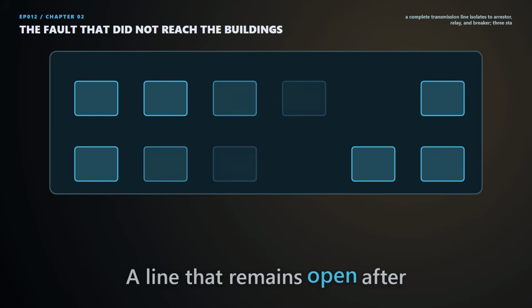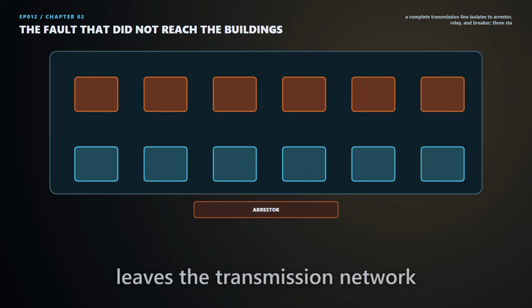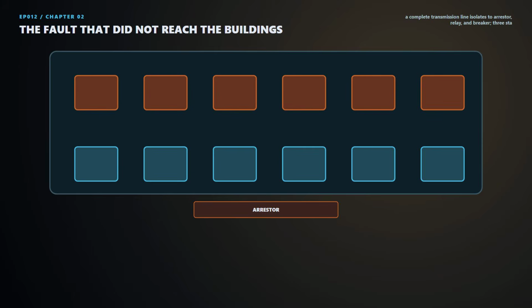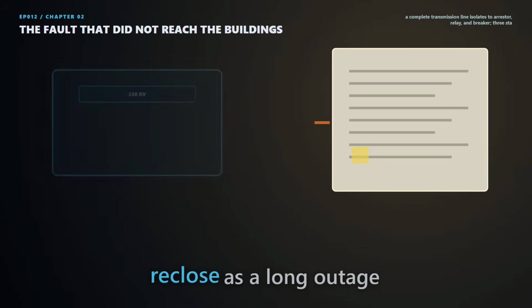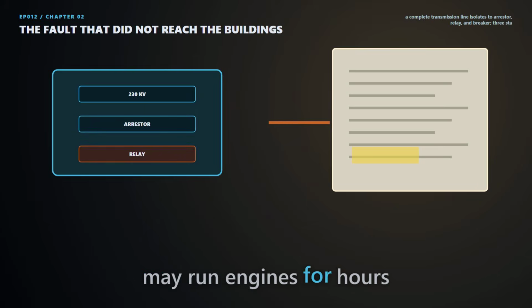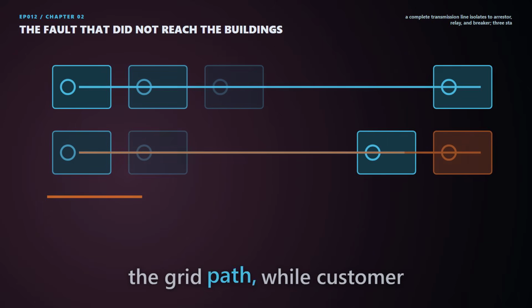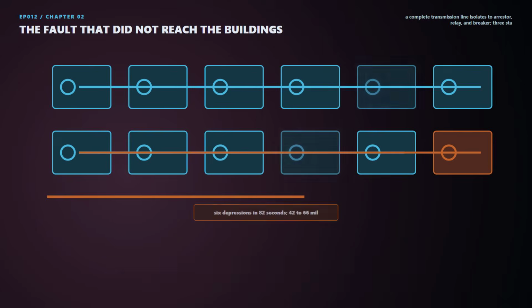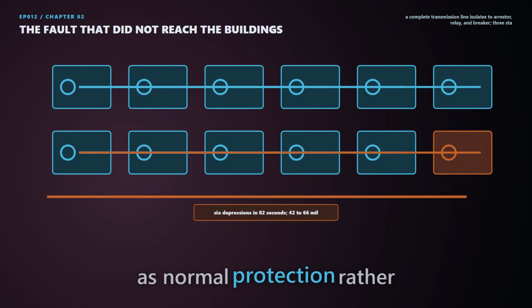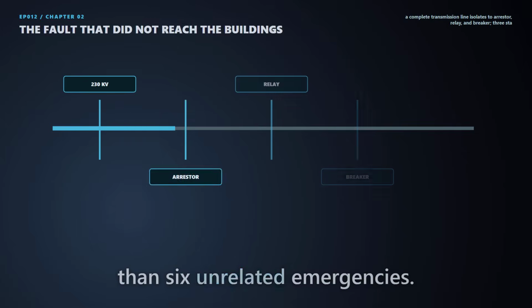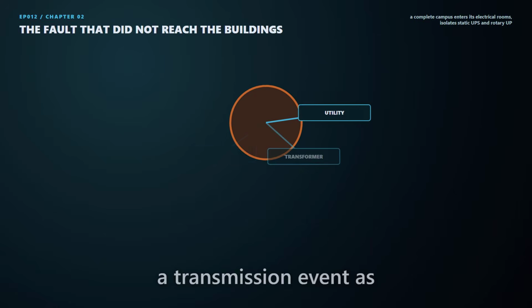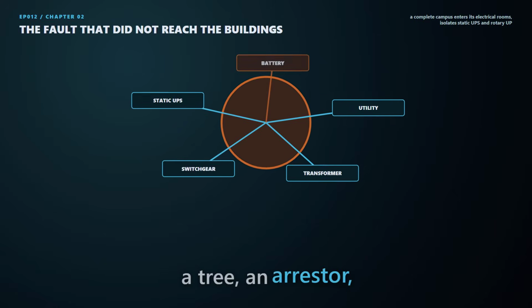A line that remains open after every temporary contact leaves the transmission network weaker until crews investigate. A campus that treats every reclose as a long outage may run engines for hours after the line is healthy. Operators need enough attempts to recover the grid path, while customer controllers need one published sequence they can recognize as normal protection rather than 6 unrelated emergencies. A server does not experience a transmission event as a tree, an arrestor, or a breaker.